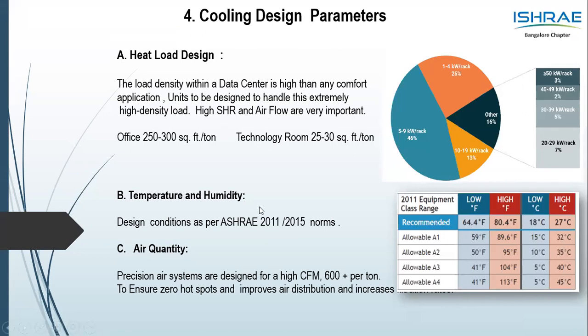The next important point: we have been checking what the downtime is, 13%, 30% on the PUE, 13% cooling loss in the report which spoke of the downtime. So for temperature and humidity, thanks to ASHRAE 2011, 2015, the recommended temperature is 18 to 27. So what is 18 to 27? It is the supply air temperature to the rack. To these racks, the supply air temperature is to be maintained between 18 to 27.